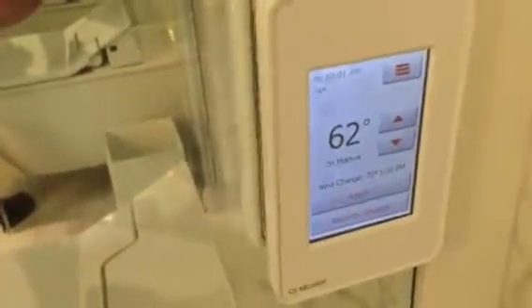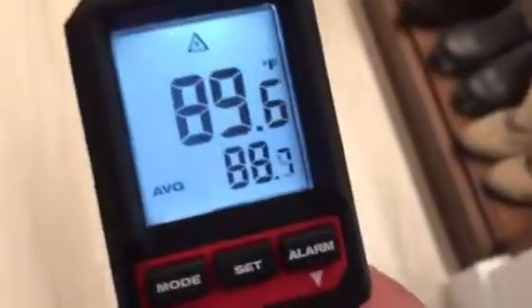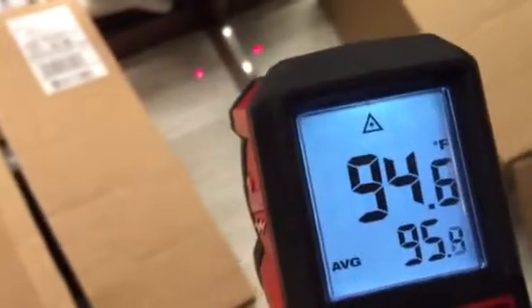Today is January 5th, 2018, and we're here at the residence. You can see the temperature setting on the thermostat and the floor setting right here. It's 95 degrees, 94 degrees on the floor, yet the thermostat temperature is set at 62 degrees.